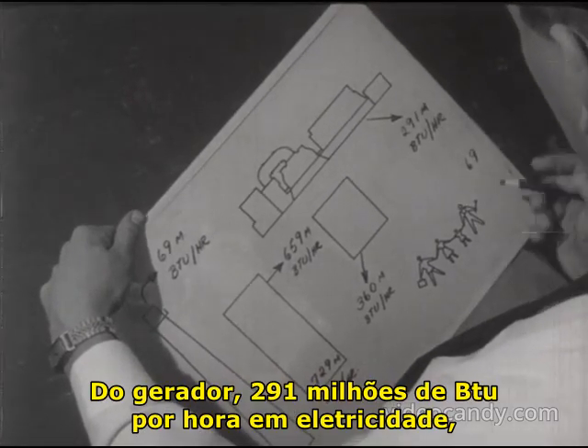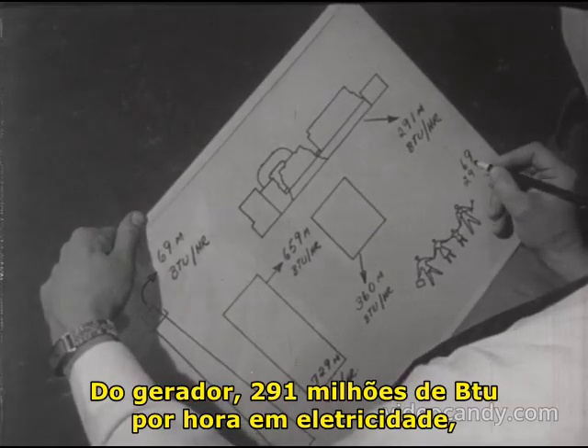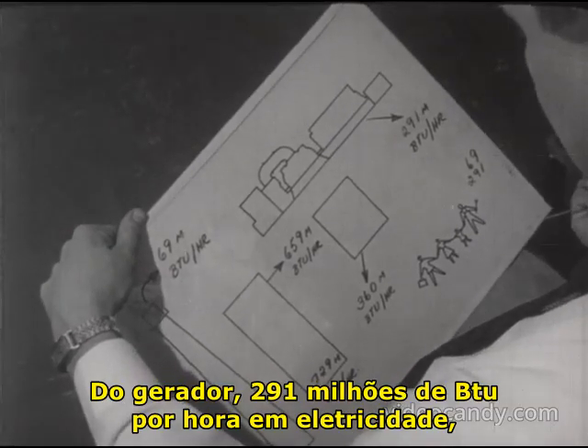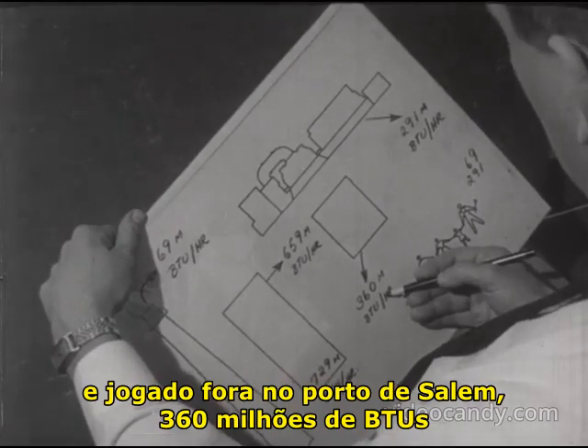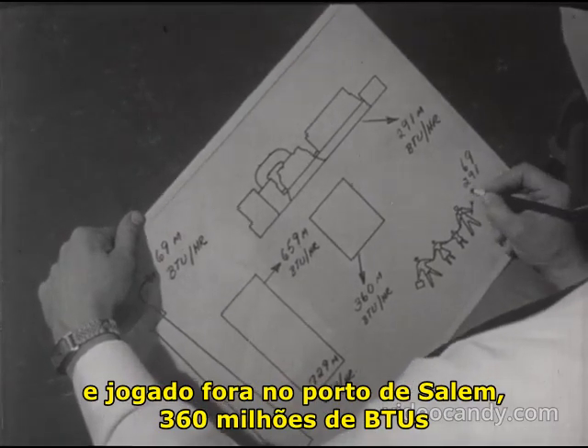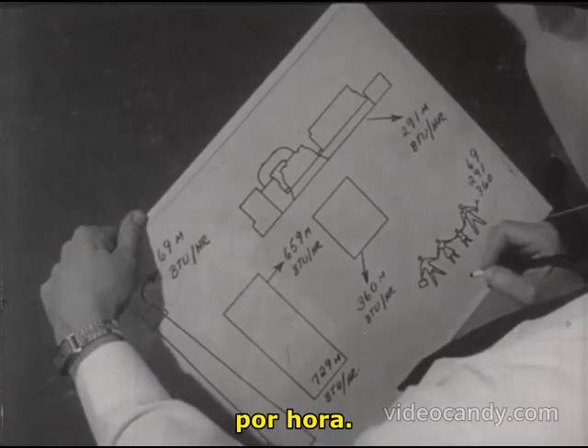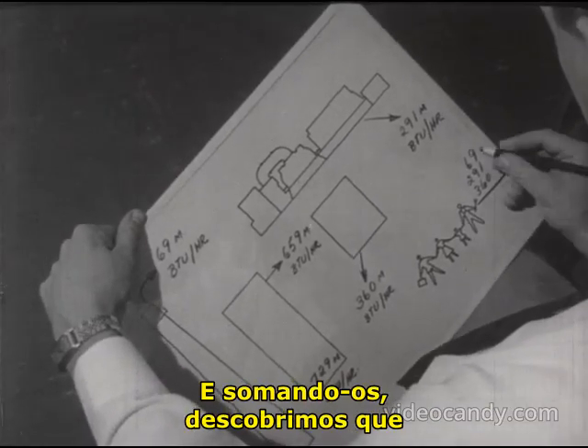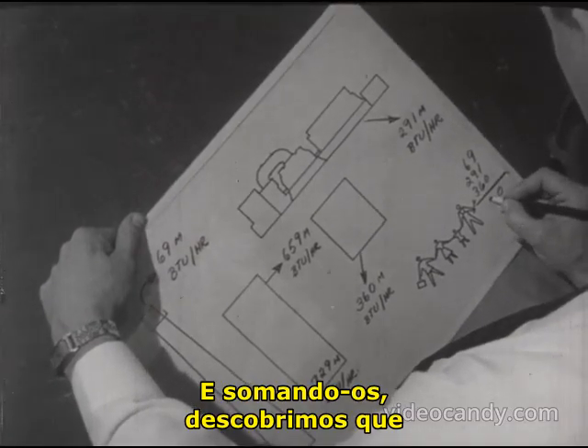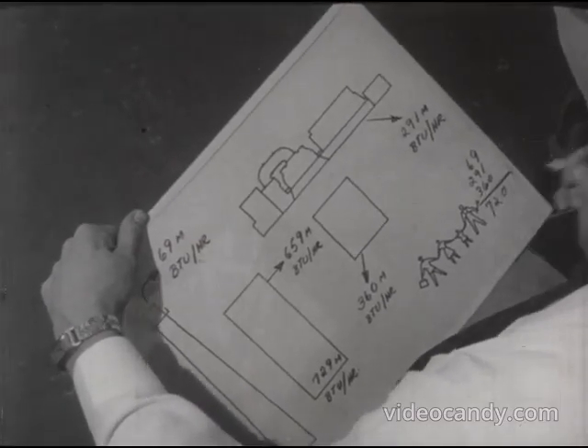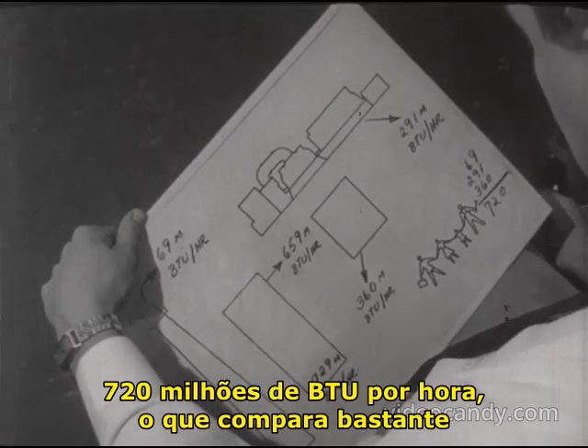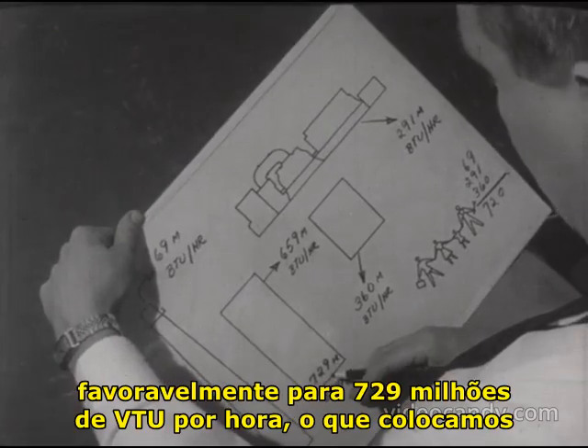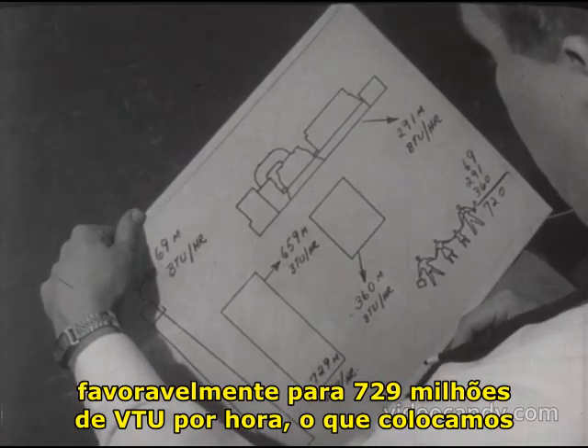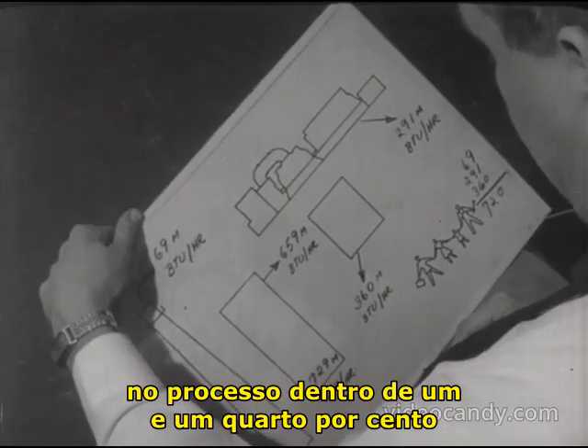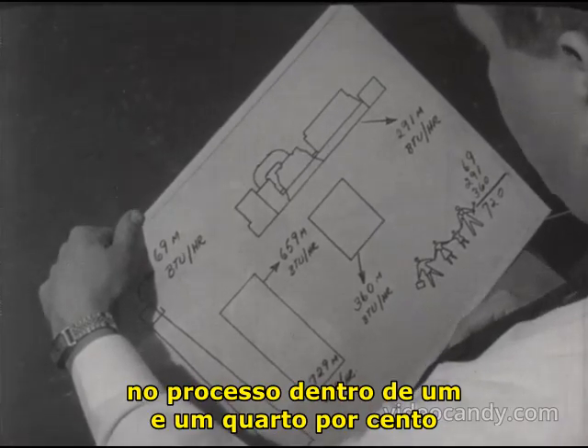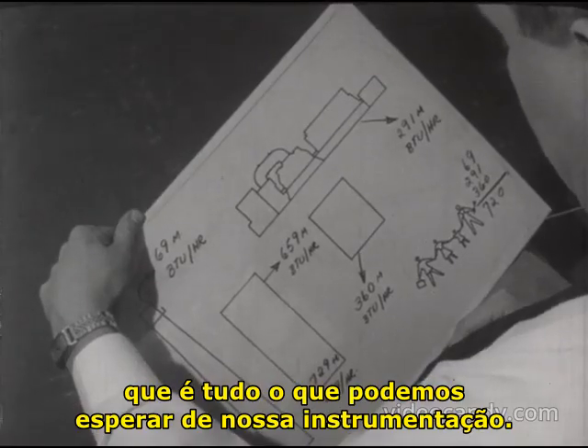Out of the generator, 291 million BTU per hour as electricity, and thrown away to Salem Harbor, 360 million BTU per hour. And adding them up, we find that we have 720 million BTU per hour, which compares quite favorably with 729 million BTU per hour, which we put into the process, within 1.25%, which is about all that we can expect from our instrumentation.